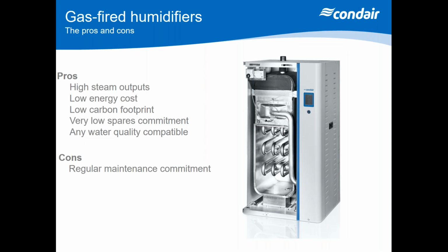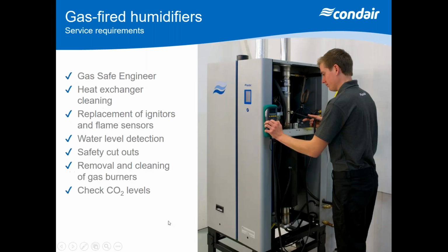The pros and cons with these is you're having to keep these heat exchangers cleaned up and remove the scale continually to make sure these heat exchangers are reaching the correct temperatures to boil the water. The other thing to consider with a gas unit is the fact you can't use a standard maintenance engineer. It's got to be gas safe, and they're going to be gas safe to a commercial ticket to actually service these units. So invariably, with these gas units, you're going to be cleaning up these heat exchangers depending on how hard your water is.